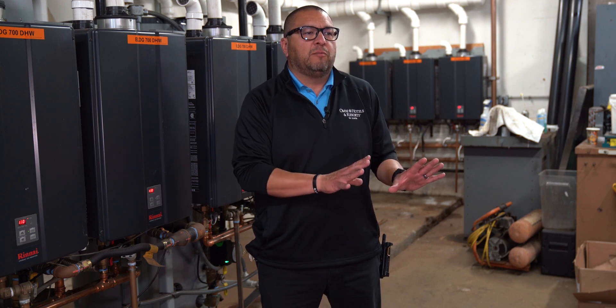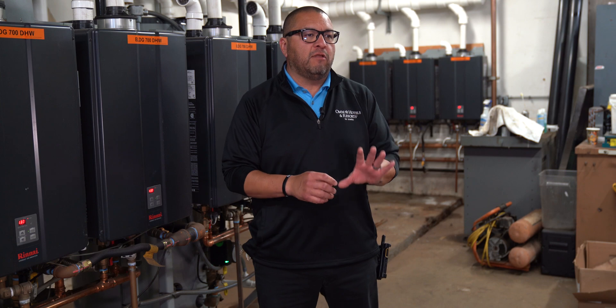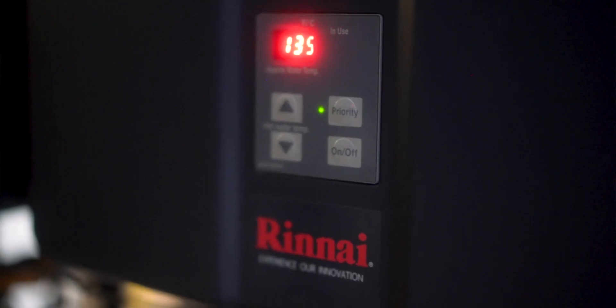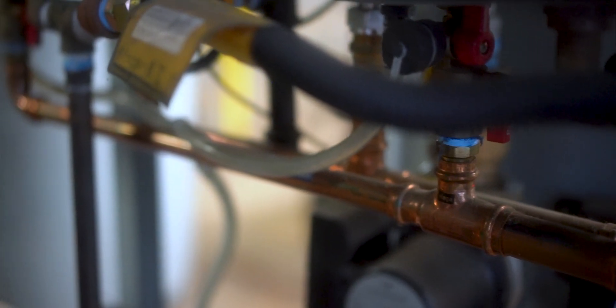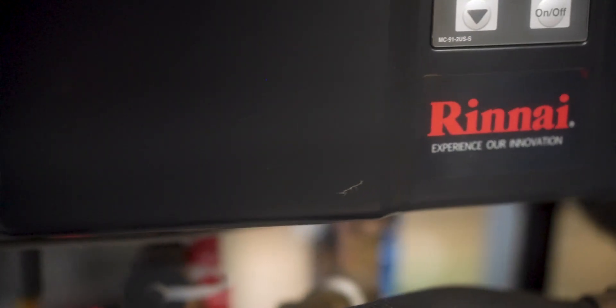I can't even begin to imagine what that savings would be now — in January 2023 here in Southern California, the cost per therm went up to $5.11 per therm. These units behind me are very reliable and pretty much hands-off. On occasion a unit will go into an error code, and the only issue we've experienced is having to clear up the strainer — take it out, clean it, and put it back in. Some of our units are fed off soft water so they don't need descaling, but the other units you just descale them once a year, and there's really nothing else to do.